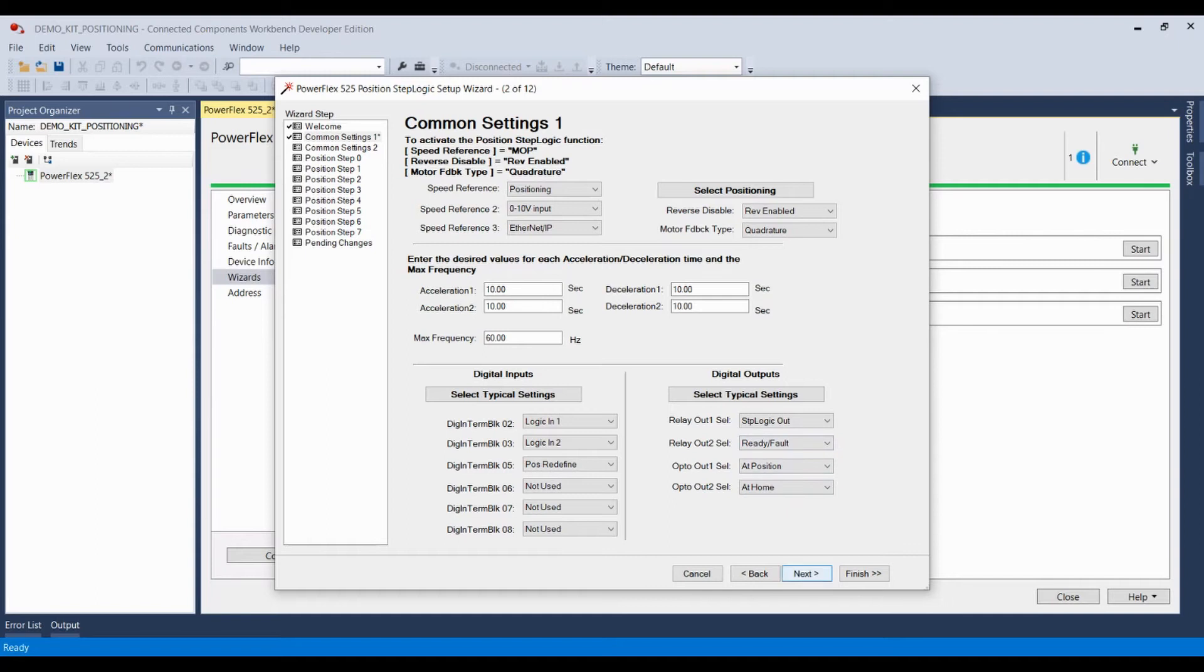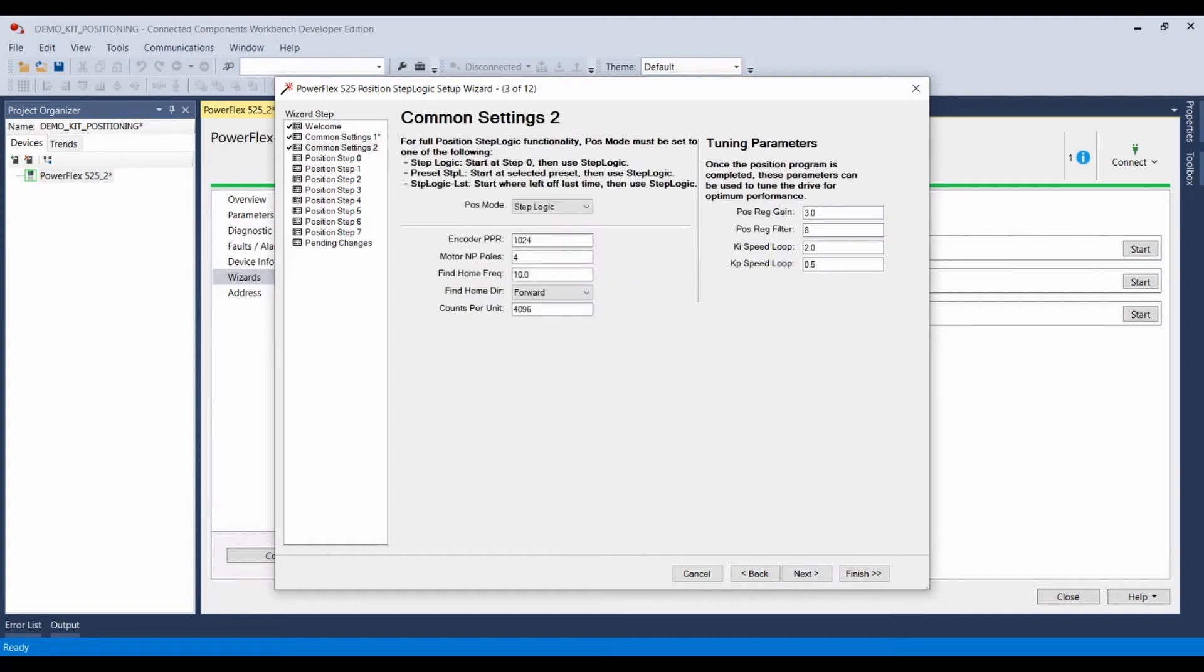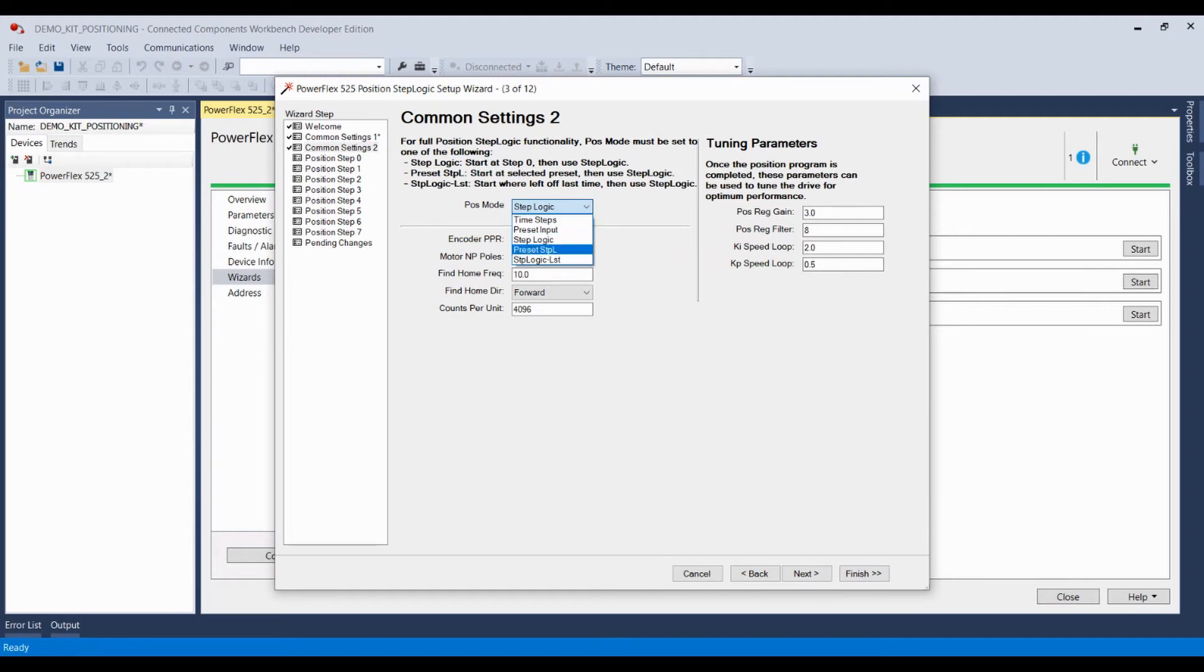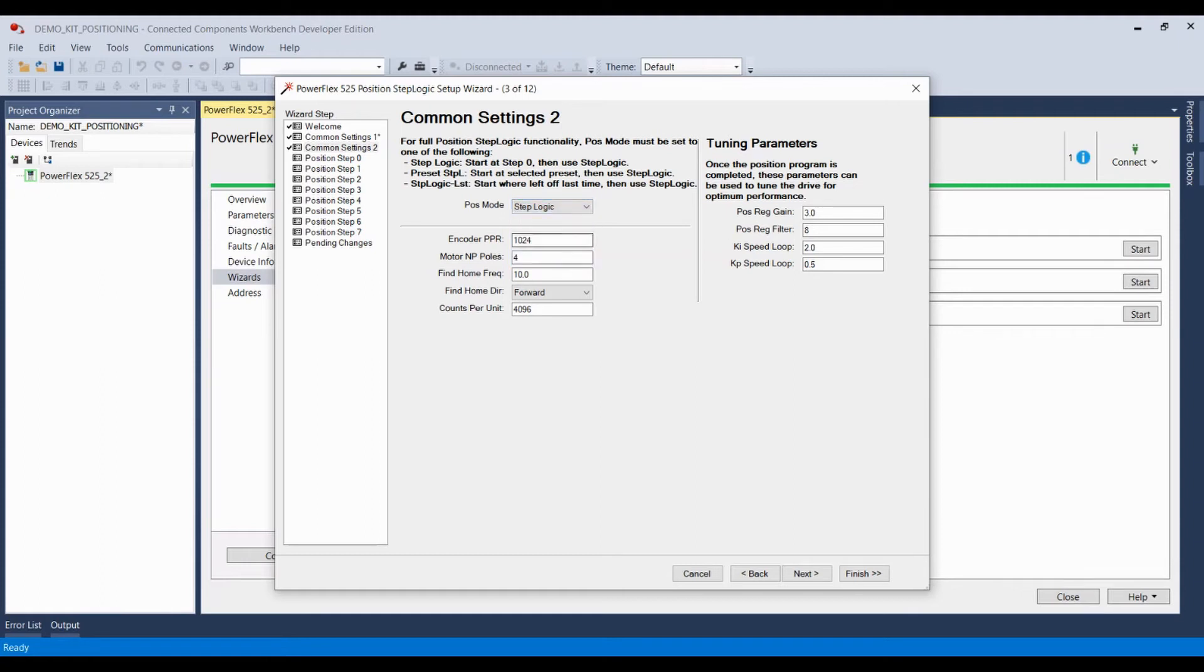Moving on to common settings two. Here we can pick our position mode. If you're going to use position step logic, this must be set to either step logic, preset step logic, or step logic list. Time steps and preset input are for velocity step logic and are much simpler and not as sophisticated as step logic itself. So we're going to set that to step logic.